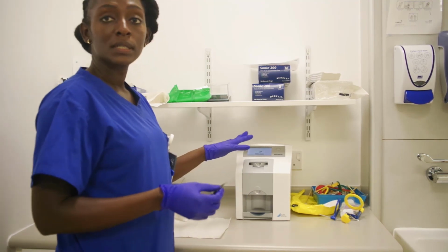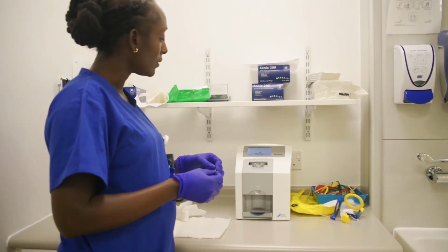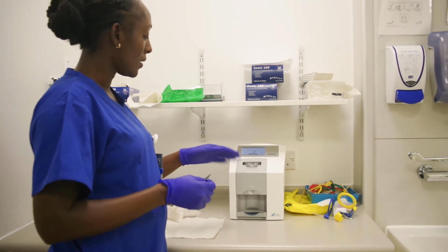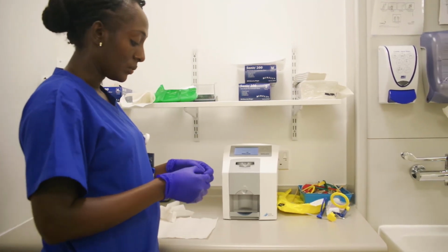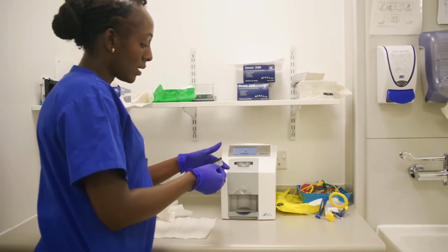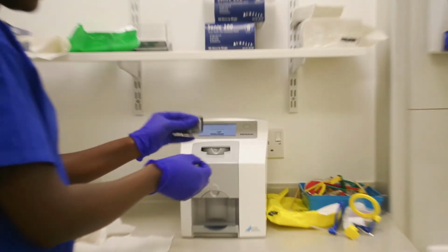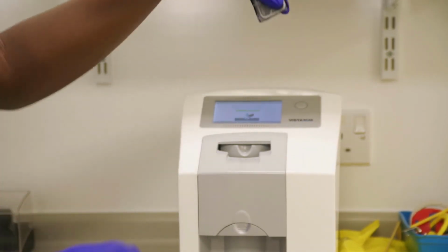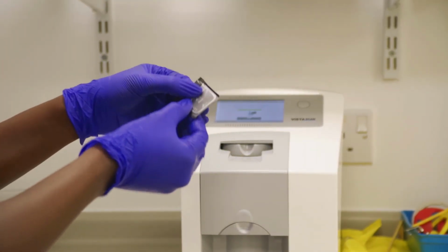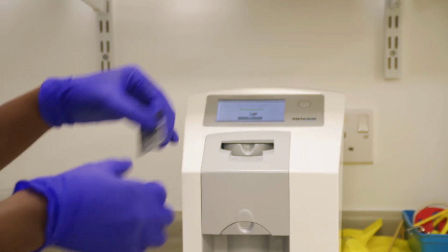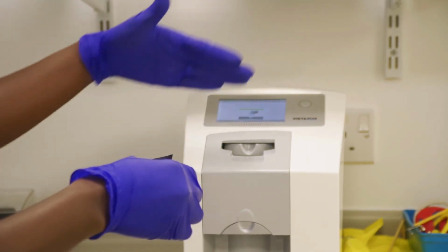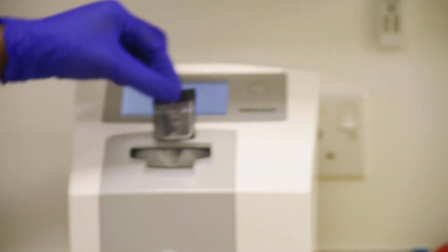This is our processing equipment, and Mark showed you this during the lecture. So this is for the indirect digital. So I'm going to process this phosphor plate. There's an indentation here and I rip that bit, okay? But you'd want to make sure that you don't expose this to light. The laser light is away from you, so you'd want to feed the phosphor plate in this way, not the other way, okay?